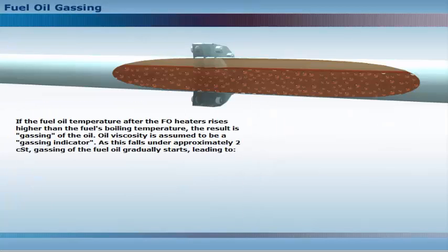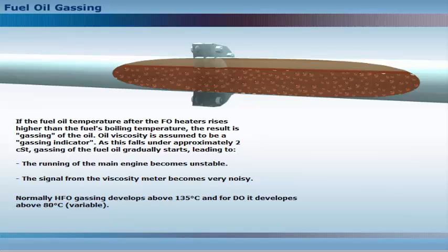If the fuel oil temperature after the fuel oil heaters rises higher than the fuel's boiling temperature, the result is gassing of the oil. Oil viscosity is assumed to be a gassing indicator. As this falls below approximately two centistokes, gassing of the fuel oil gradually starts, leading to unstable running of the main engine. The signal from the viscosity meter becomes very noisy. Normally, heavy fuel oil gassing develops above 135 degrees Celsius, and for diesel oil, it develops above 80 degrees Celsius.